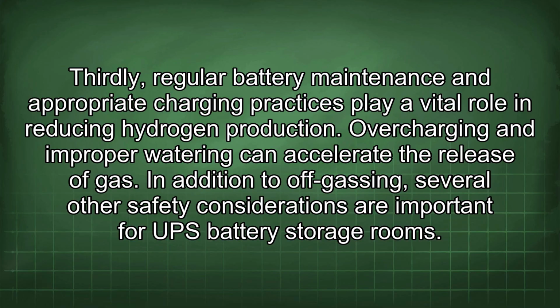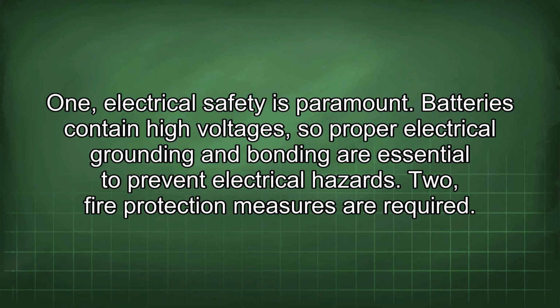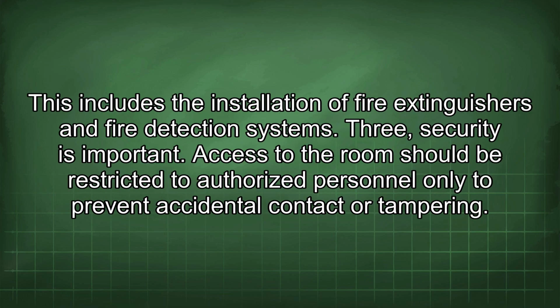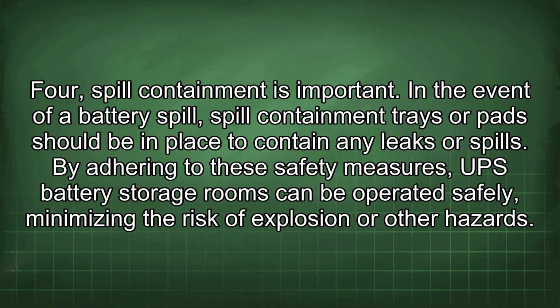In addition to off-gassing, several other safety considerations are important for UPS battery storage rooms. 1. Electrical safety is paramount. Batteries contain high voltages, so proper electrical grounding and bonding are essential to prevent electrical hazards. 2. Fire protection measures are required. This includes the installation of fire extinguishers and fire detection systems. 3. Security is important. Access to the room should be restricted to authorized personnel only to prevent accidental contact or tampering. 4. Spill containment is important. In the event of a battery spill, spill containment trays or pads should be in place to contain any leaks or spills.